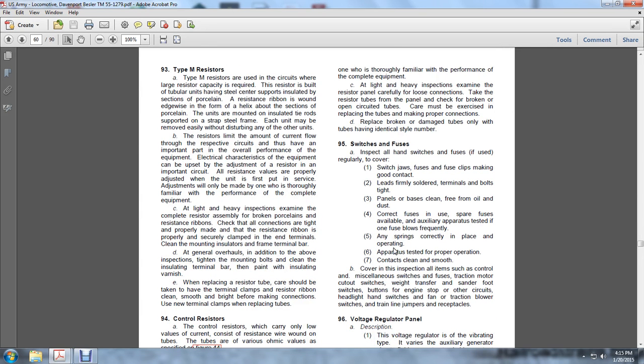93. The type M resistor. The type M resistors are used in circuits where large resistor capacity is required. The resistor is a built-up tubular unit having a steel center to support insulated sections of porcelain. A resistance ribbon is wound edgewise in a helix on the former and sections of porcelain. The units are mounted on insulated tie rods supported by the strap steel frame. Each unit may be removed easily without disturbing any of the other units.